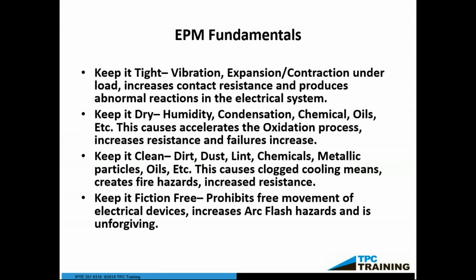Fundamentals we need to talk about: keep it tight, because vibration, expansion, and contraction wreck our system. Keep it dry - humidity, condensation, chemicals, oils cause accelerated oxidation processes and give us failures. Keep it clean - dirt, dust, lint, chemicals, metallic particles, and oils clog our cooling systems and create fire hazards and increase resistance. And keep it friction-free - friction prohibits free movement of electrical devices, increases arc flash hazards, and is very unforgiving.